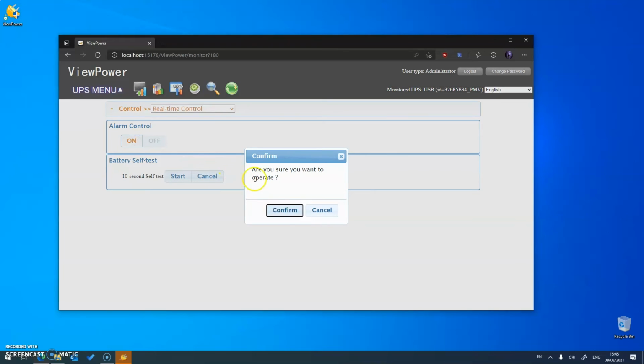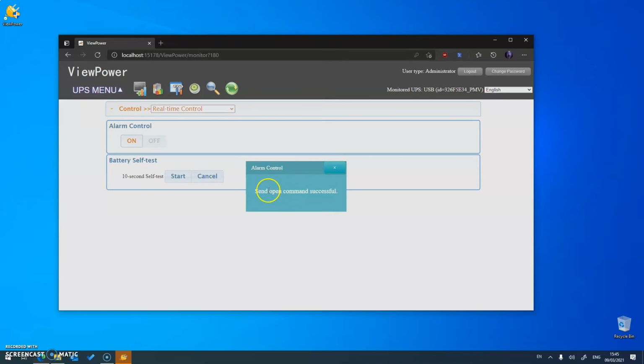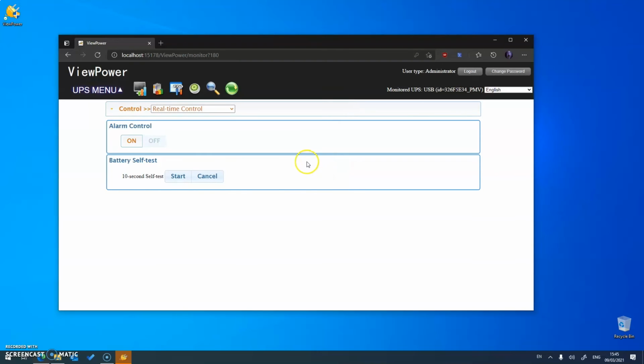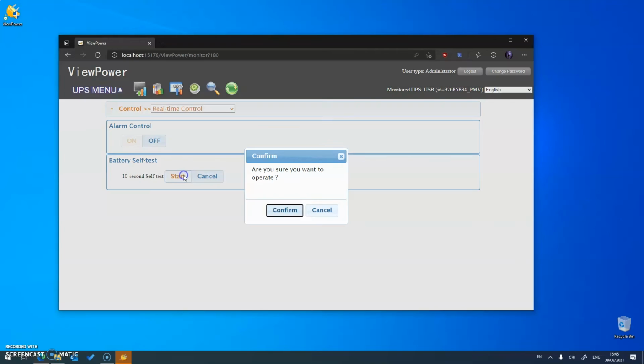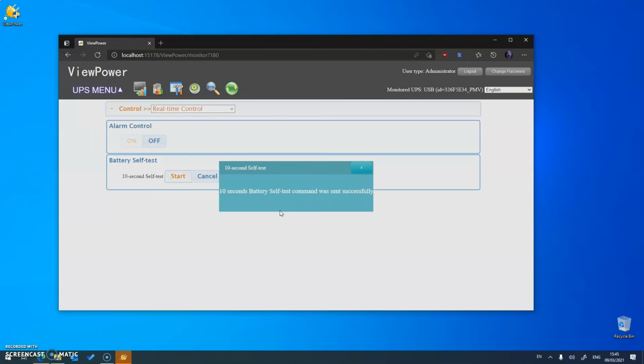So I'm going to go back ahead and turn the UPS back on. Also from this screen you can start a battery self-test, which should identify if there's any problems with the internal battery. So I'll check that now. Press start, confirm.